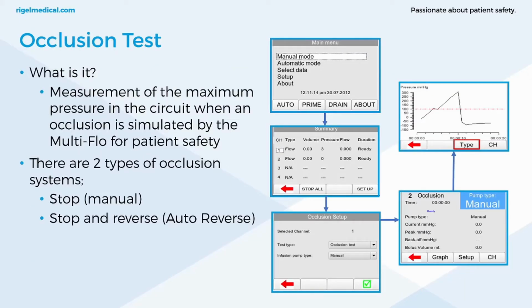So we've got manual mode occlusion test. What is it? It's the measurement of the maximum pressure in the circuit when an occlusion is simulated by the Multi-Flo for patient safety. So if you're running a flow rate from the infusion device, the Multi-Flo is just producing a back pressure and simulating an occlusion in that circuit. There are 2 types of occlusion systems: stop manual and stop and reverse.